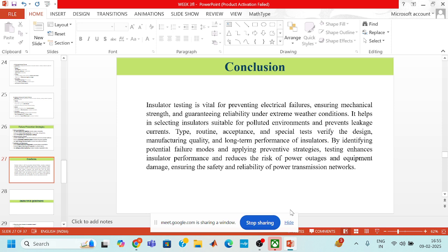So type test, routine test, acceptance test, and special test. These all verify the design, manufacturing quality, and long-term performance of insulators. By identifying potential failure modes and applying preventive strategies, testing enhances insulator performance and reduces the risk of power outages and equipment damage, ensuring the safety and reliability of power transmission networks. So based on this presentation and the previous two, there are some objective questions.